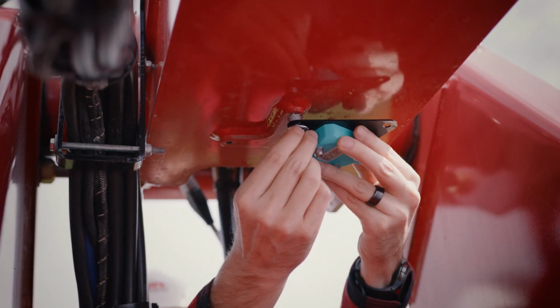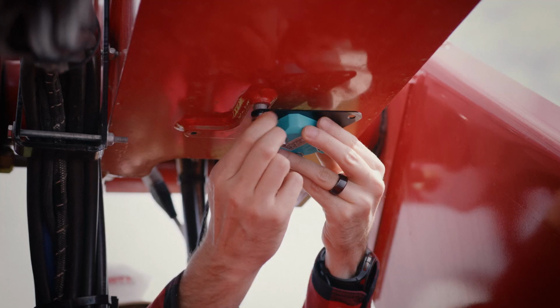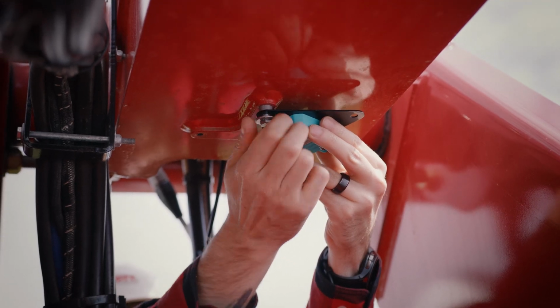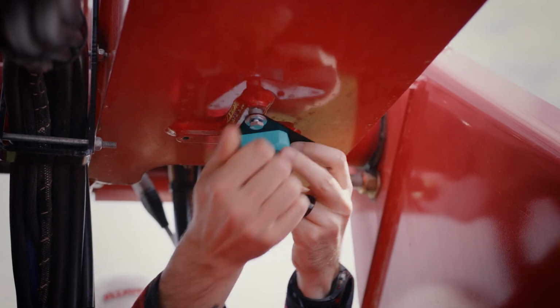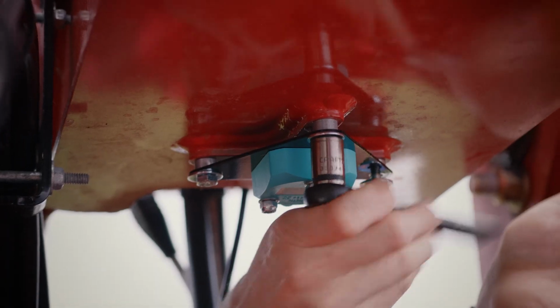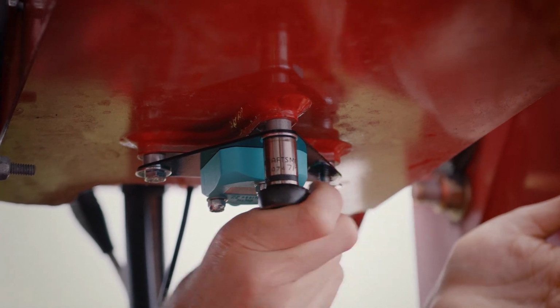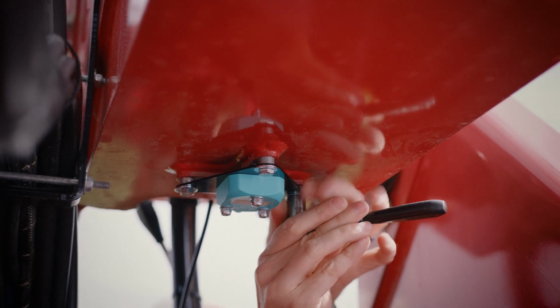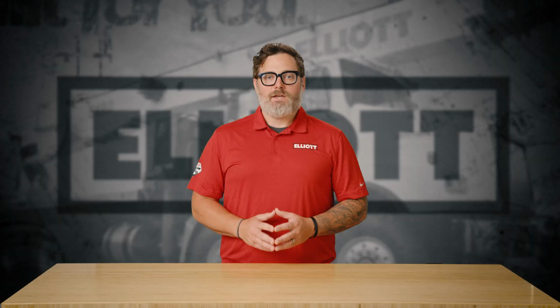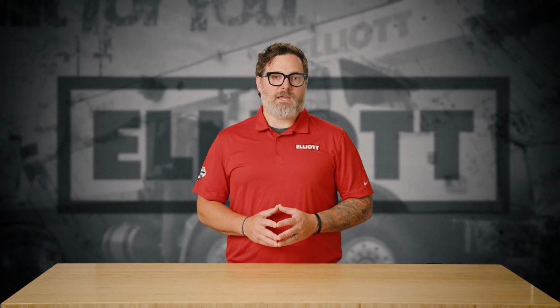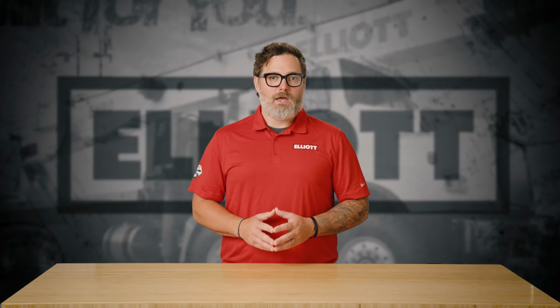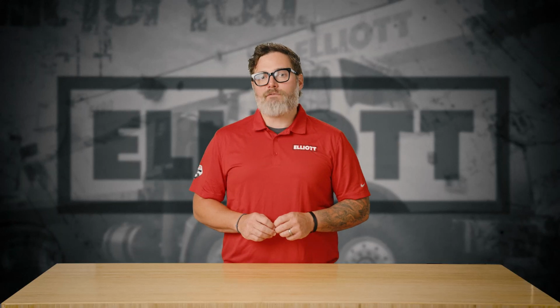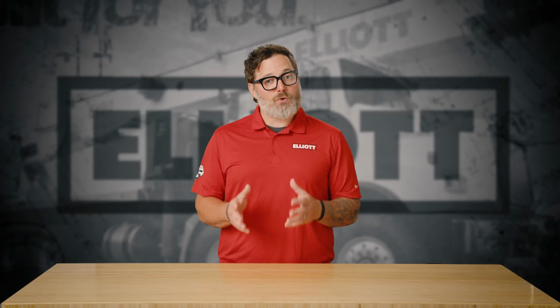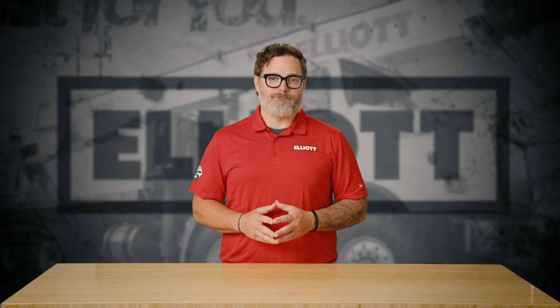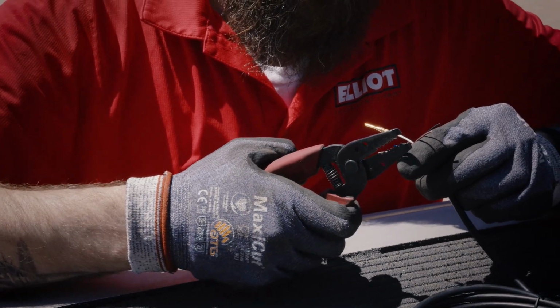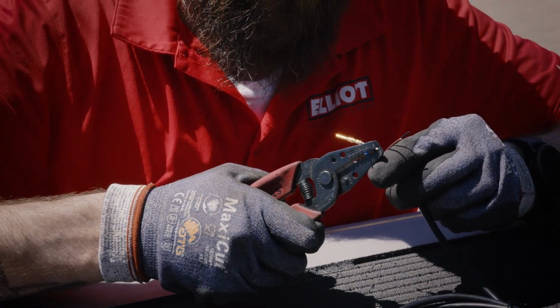With the Posital sensor secured to the adapter plate, mount the assembly to the bottom of the boom using the supplied 7/16 hardware and spacers. Make sure the spacers are seated correctly and the adapter plate sits flat against the boom mounting surface. Now we'll terminate the flying leads of the cable into the supplied Deutsch connector. Pay close attention to the wire to cavity assignments. Getting this right is critical for proper sensor operation. Crimp each wire into its assigned cavity using the Deutsch terminal crimping tool.